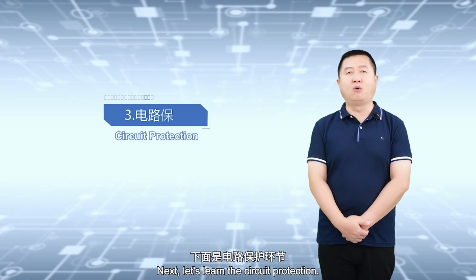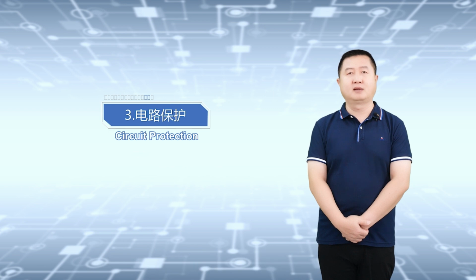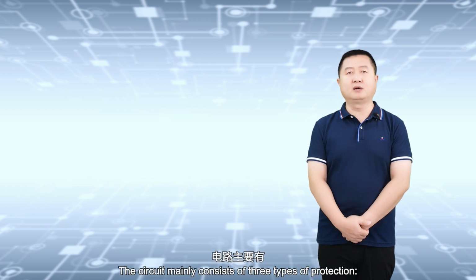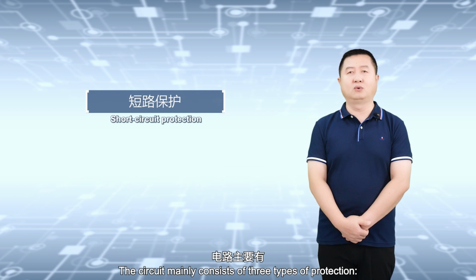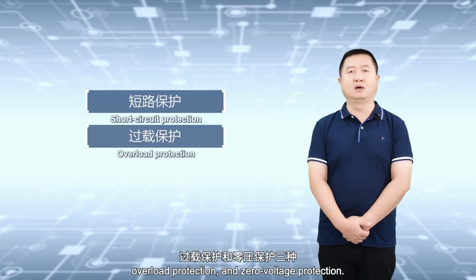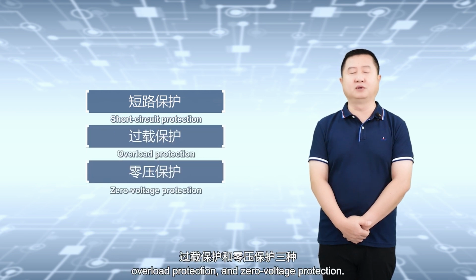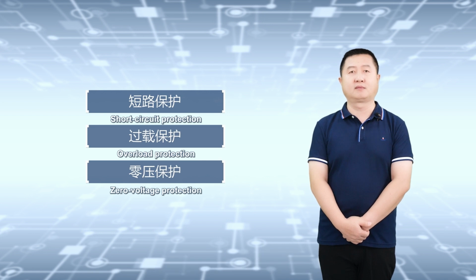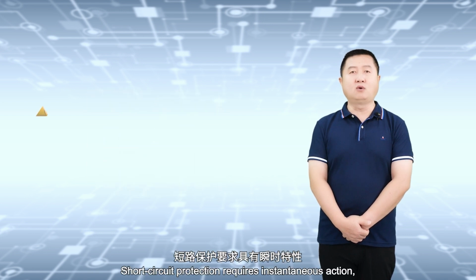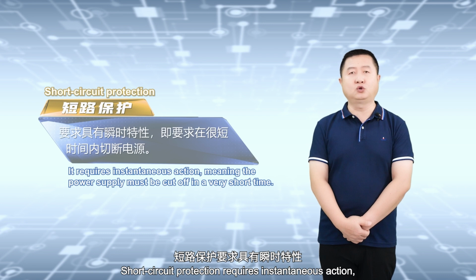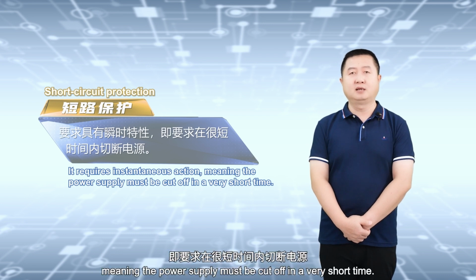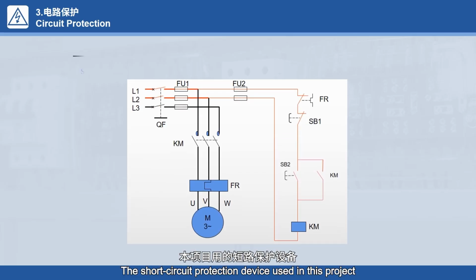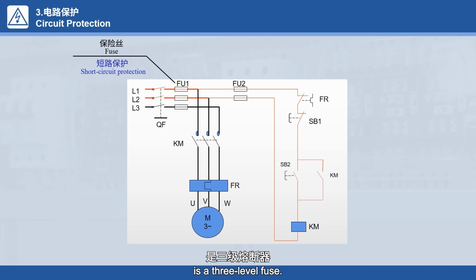Next, let's learn the circuit protection. The circuit mainly consists of three types of protection: short circuit protection, overload protection, and zero voltage protection. Short circuit protection requires instantaneous action, meaning the power supply must be cut off in a very short time. The short circuit protection device used in this project is a 3-level fuse.